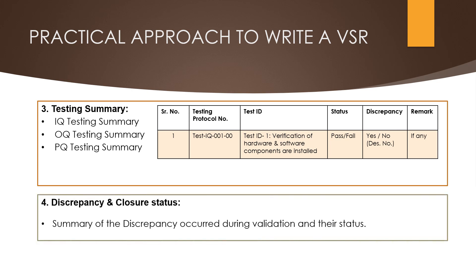The fourth component of the validation summary report is the discrepancy and closure status. In this section we need to define all discrepancy details observed from start to end of the validation activities. For example: test ID details, test step details, discrepancy number, discrepancy details, resolution of that discrepancy, and the closure status. We can make a table and provide the relevant details, including discrepancy and closure status.